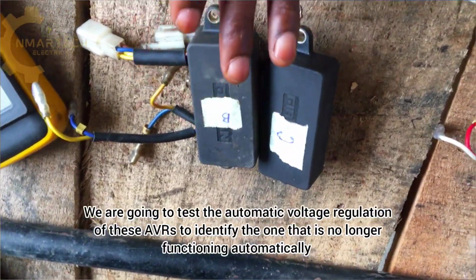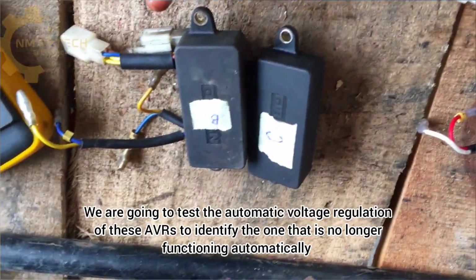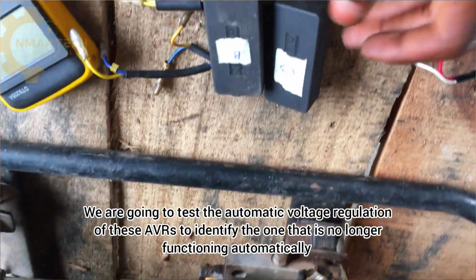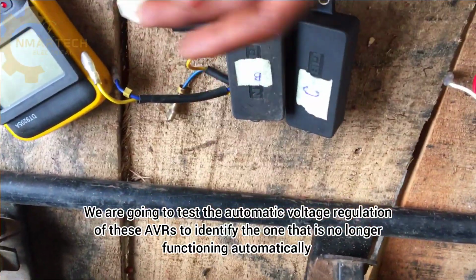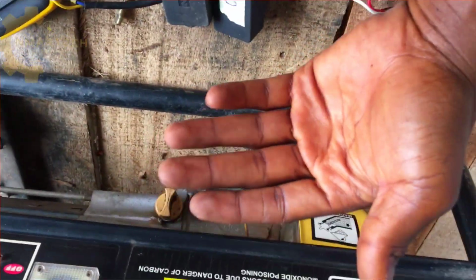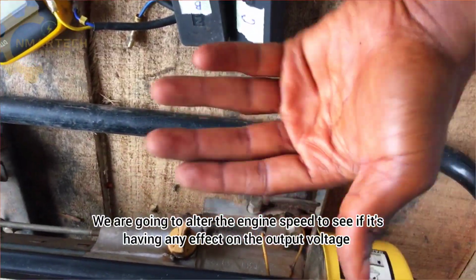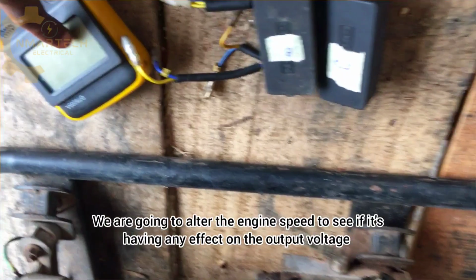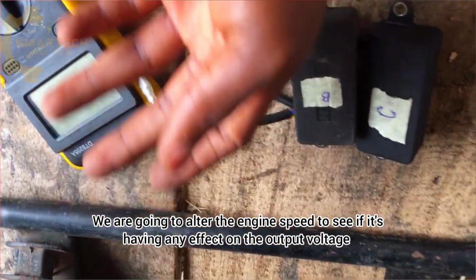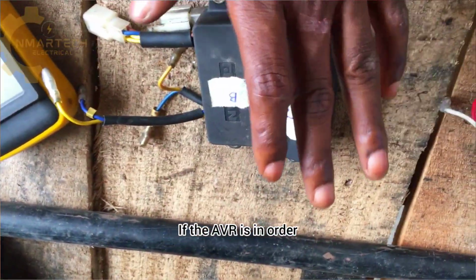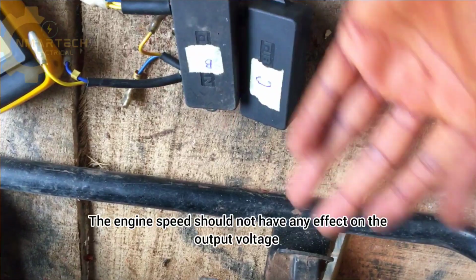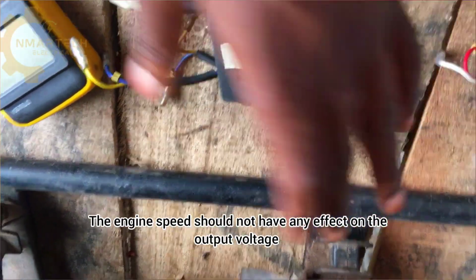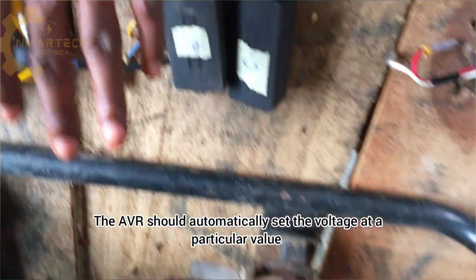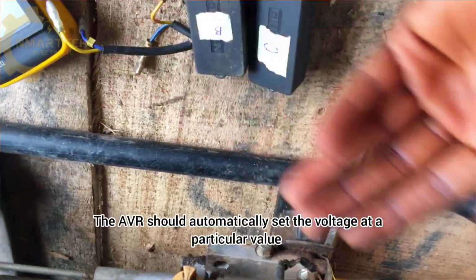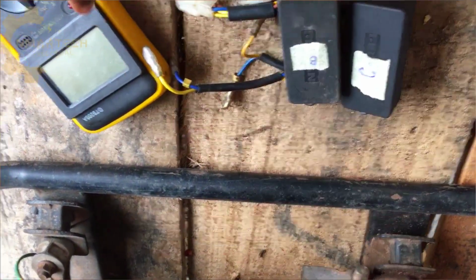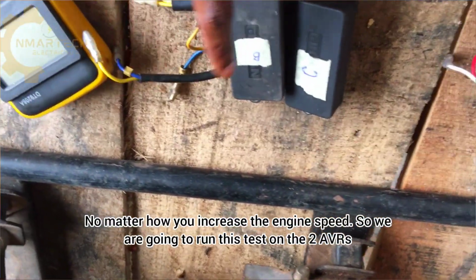We are going to test the automatic voltage regulation of these AVRs to identify the one that is no longer functioning automatically. So we are going to alter the engine speed to see if it's having any effect on the output voltage. If the AVR is in order, the engine speed should not have any effects on the output voltage. The AVR should automatically set the voltage at a particular value, no matter how you increase the engine speed.